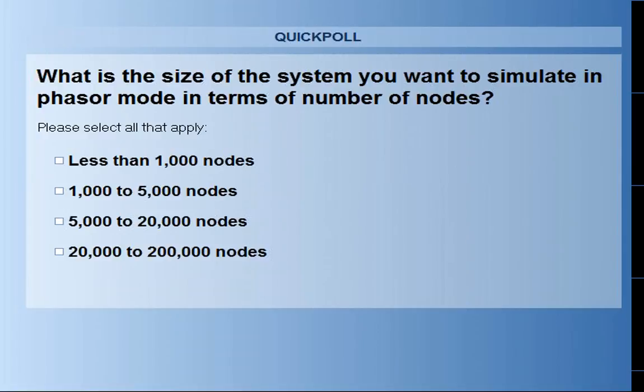The phasor part is done in the ePHASORSIM, and the EMT part is done with the SPS sim power system blocks in the Simulink MATLAB. The time step in EMT part was 50 microseconds, and in phasor type was 10 milliseconds. So we have tested these, and we are able to do.